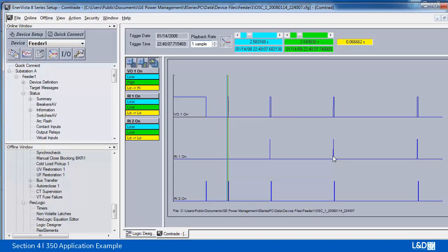publish just 2 remote outputs, and the 850 uses these 2 remote inputs to set its latch gate. So there are always different ways to program this GOOSE message, the processing, and the protection scheme. So that concludes this demo part of the auto reclose.